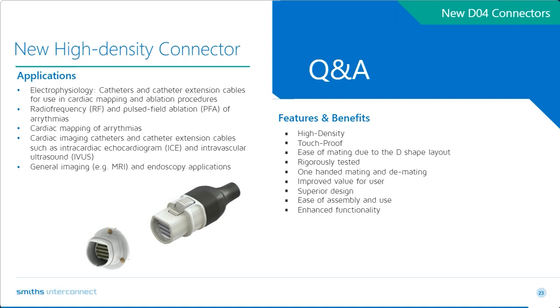Next question: how is the 2 kV withstand voltage achieved? Is that with a custom insert to increase the air clearance between contacts? Yes, exactly that. It's a custom insert that's staggered axially between contact pairs, so one pair can be offset axially from the next. That allows the creepage and clearance to increase, which gives us the ability to hit that 2,000 volt mark.